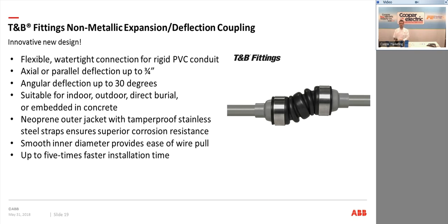Particularly in expansion deflection applications, it has axial or parallel deflection up to 3/4 inch, and angular deflection capability up to 30 degrees from a stationary point. It's suitable for indoor, outdoor, direct burial. I've sold into applications where we've direct buried this encased in concrete, connecting two vaults within a sewage system. To embed it in concrete, you do have to wrap it in a protective boot. There are installation guidelines and instructions that come with it for that application.